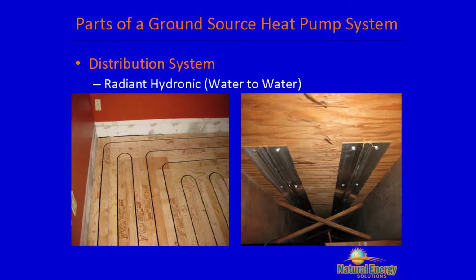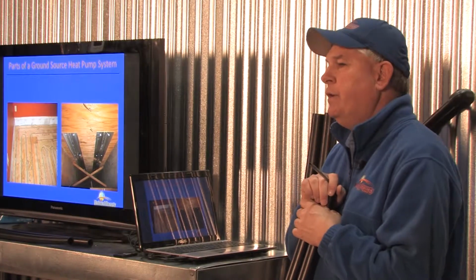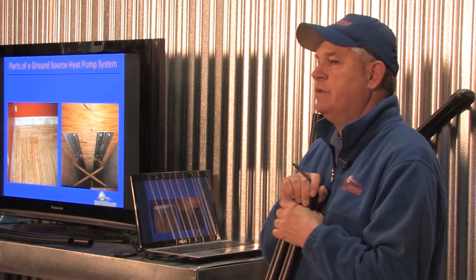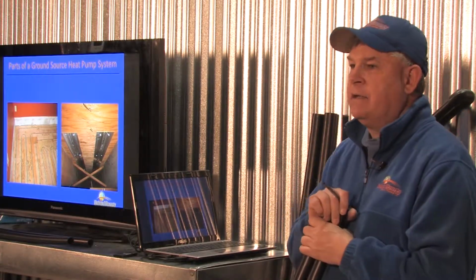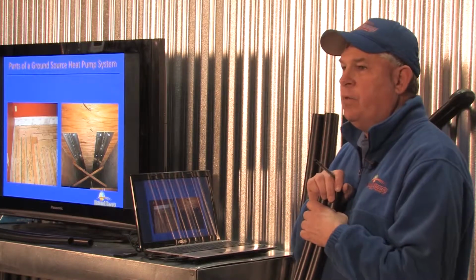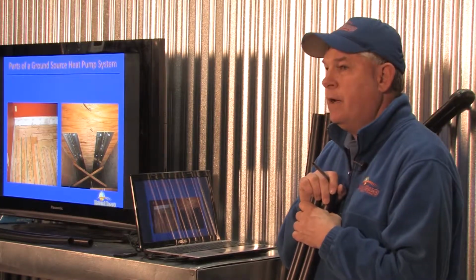So, we can have hydronic systems. Radiant floor heat. That's what this material is. Hot floors. You also may have heard that geothermal will not work with baseboard heat, which is just not true anymore. There are units out there, which we have, that will work with baseboard heat or radiators. Okay? When we're dealing with a hydronic or water system, radiant's more prevalent, but we can interchange with a boiler right now. We can make 150, 155 degree water. So you can have a hydronic system.